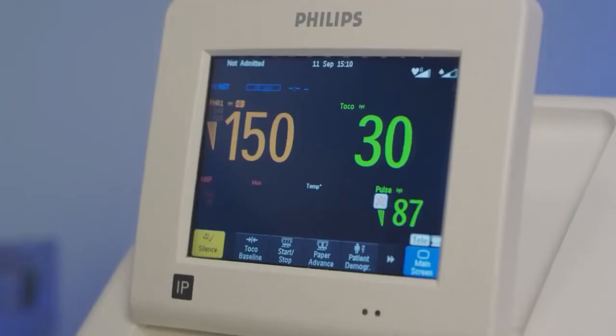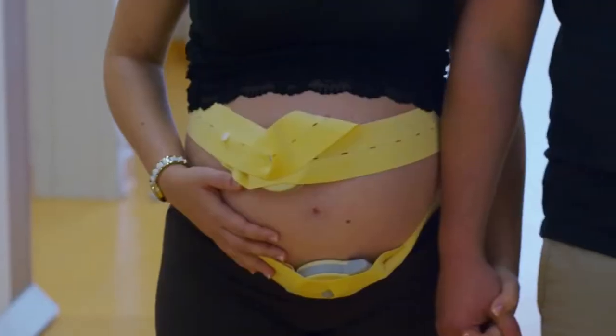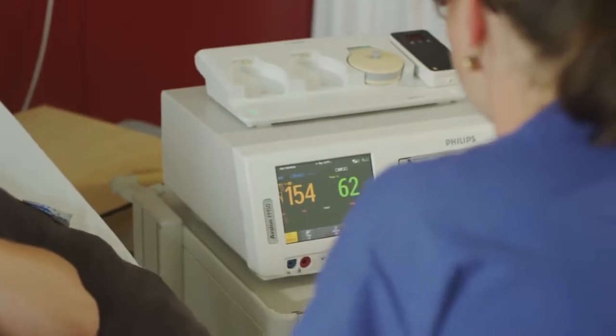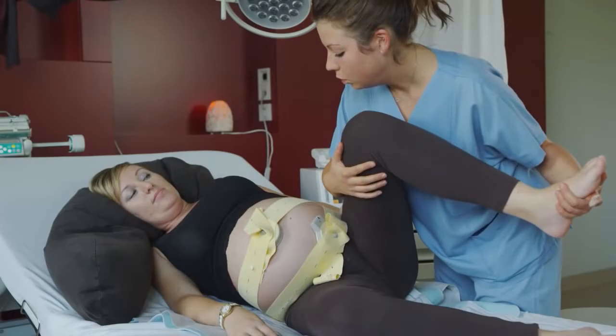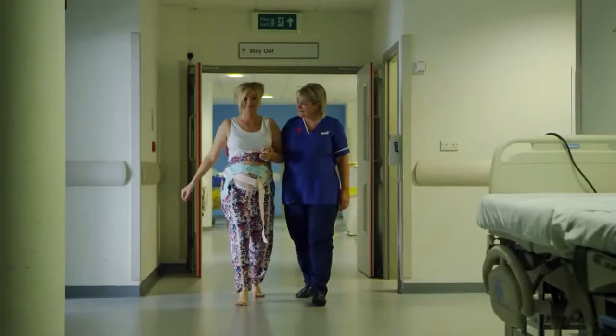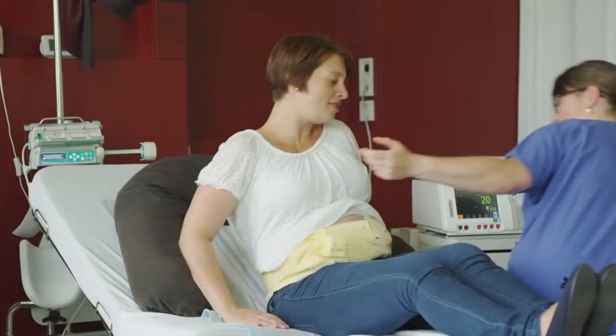The fetal heart rate and the activity of the uterine muscle are detected by two transducers placed on the mother's abdomen — one above the fetal heart to monitor heart rate, and the other at the fundus of the uterus to measure frequency of contractions. Doppler ultrasound provides the information which is recorded on a paper strip known as a cardiotocograph. External tocodynamometry is useful in showing the beginning and end of contractions as well as frequency, but not the strength of contractions.